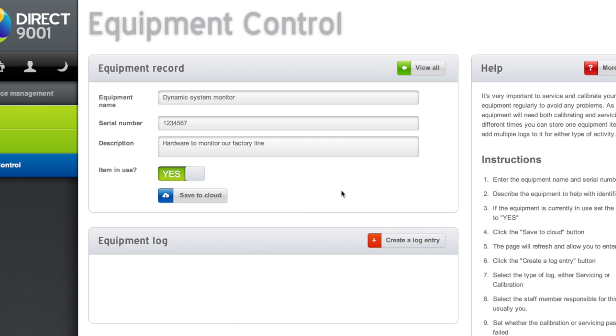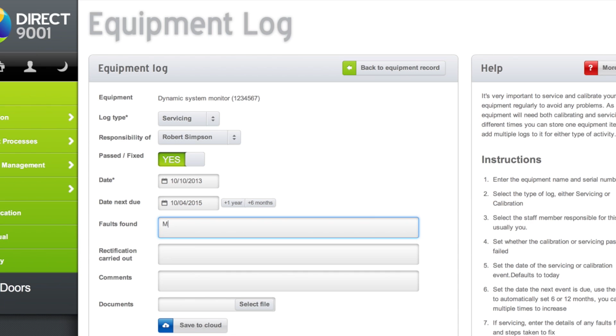Set whether the calibration or servicing passed or failed. Set the date the servicing or calibration took place. Set the date the next event is due. Use the buttons to automatically set 6 or 12 months. You can press them multiple times to increase.